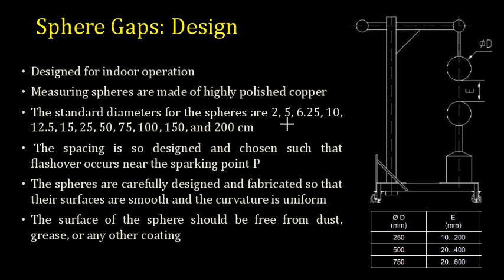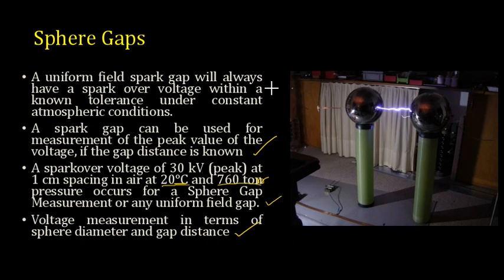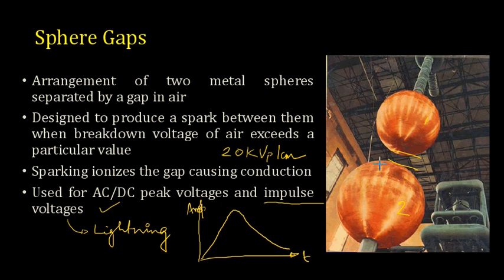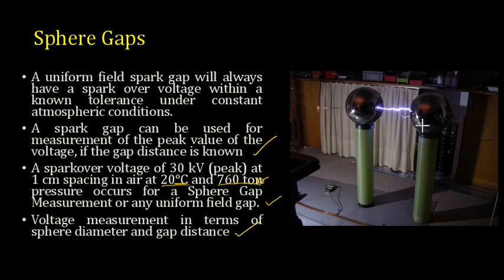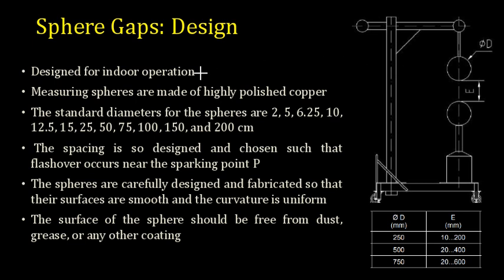Now this particular sphere gap is designed for indoor operation. You must have identified that there are two types of sphere gaps. This one is a vertical arrangement, and here you have a horizontal arrangement. Both are designed for indoor operation. These spheres are made of highly polished copper, and you can have different standard diameters of the spheres. Depending on the diameter, you have to apply different voltages. The spacing is designed in such a way that the flashover occurs near the sparking point. So this is your sparking point P, and your flashover will occur somewhere around that point.